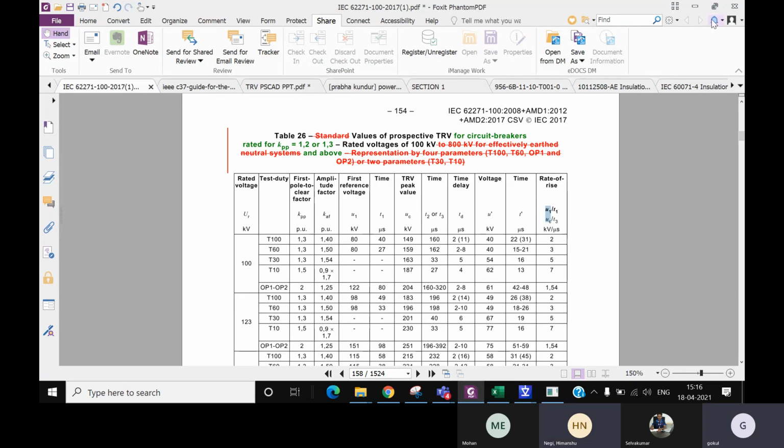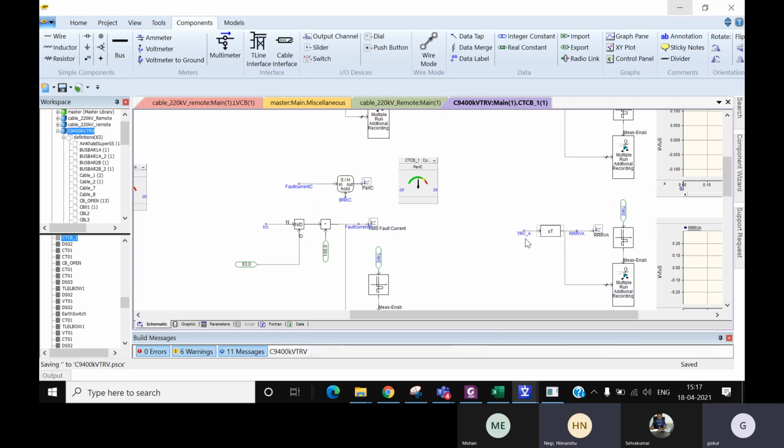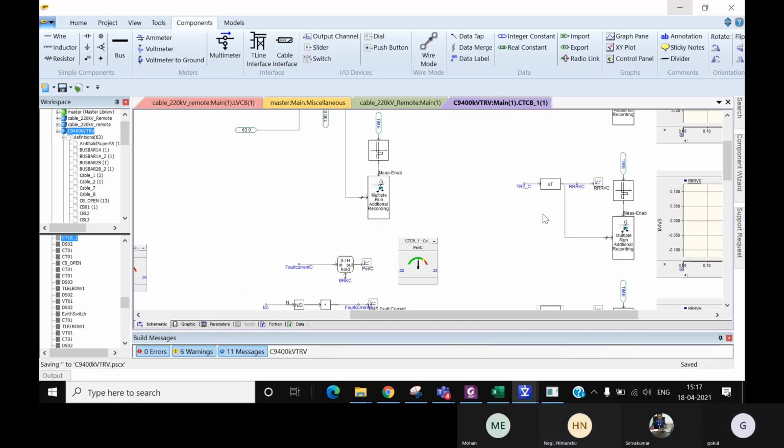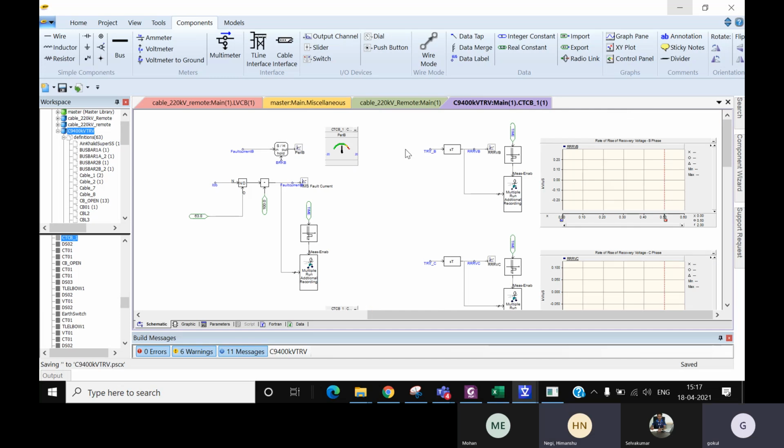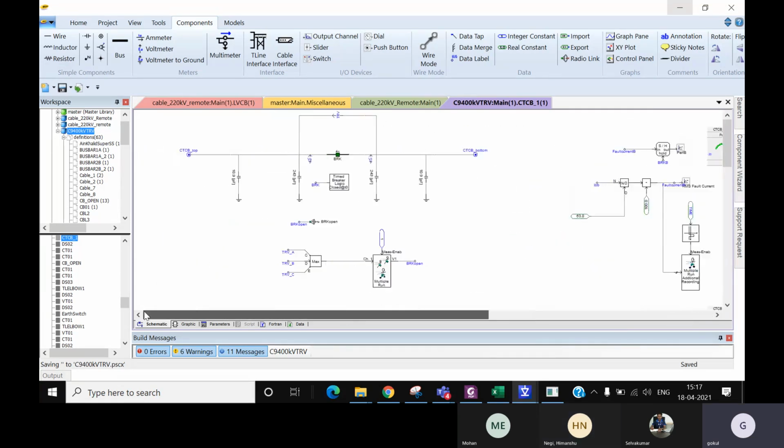So I get the KV from the TRV calculation, and then you are dividing by microsecond. Yes, exactly. That value only I was asking, like how do you reach that 0.0001? So, KV per microsecond. That is the basic formula or basic definition for TRV. Yes, this is much based on any control system, PSCAD. But this is very basic for TRV.